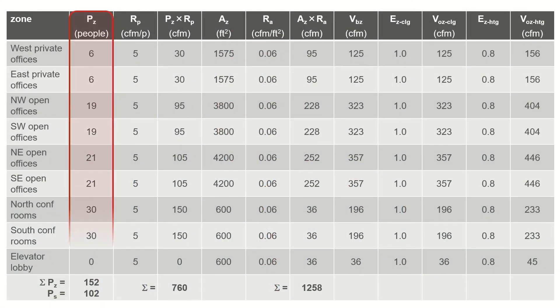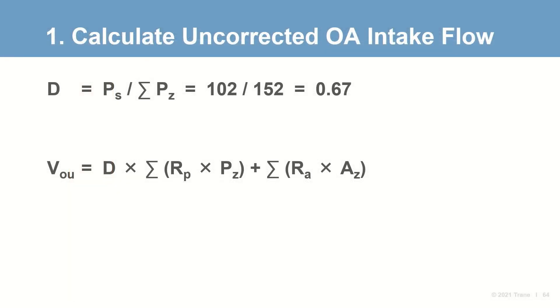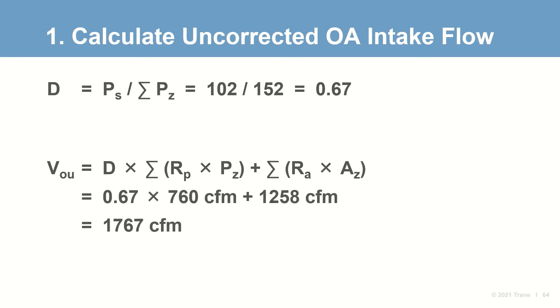This diversity can be accounted for when designing a multiple zone recirculating system. Summing the design population for each zone P-sub-Z gives 152 people, but the design team estimates the largest number expected to occupy this floor is 102 people — the design system population P-sub-S as defined by the standard. So the Occupant Diversity Ratio D is calculated to be 0.67, and the uncorrected outdoor air intake flow V-sub-OU is 1,767 CFM.